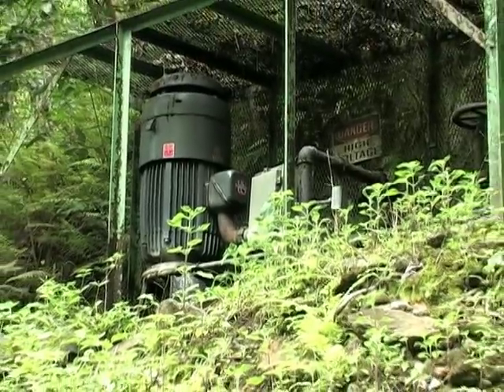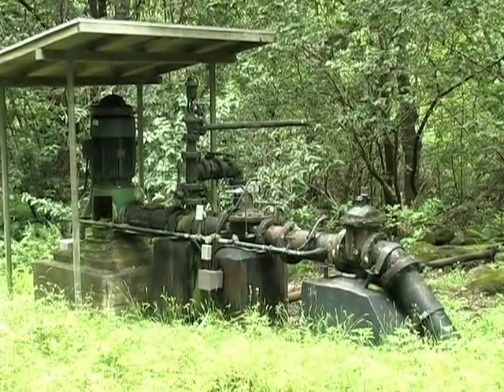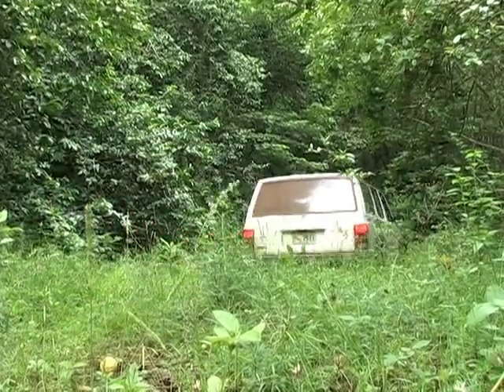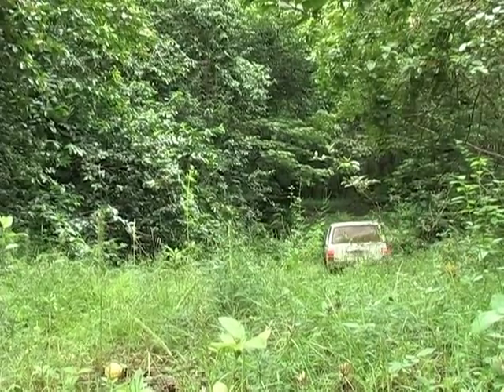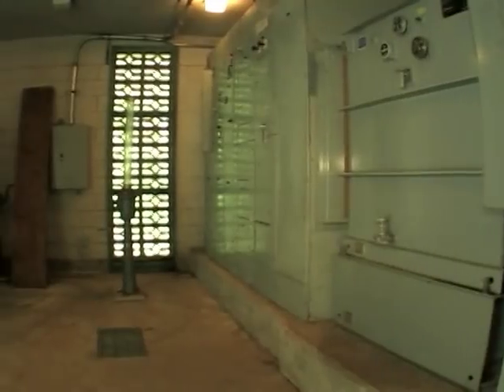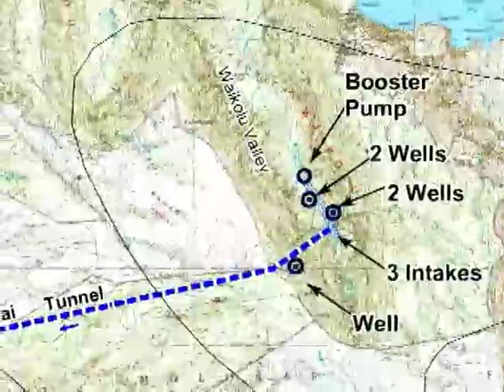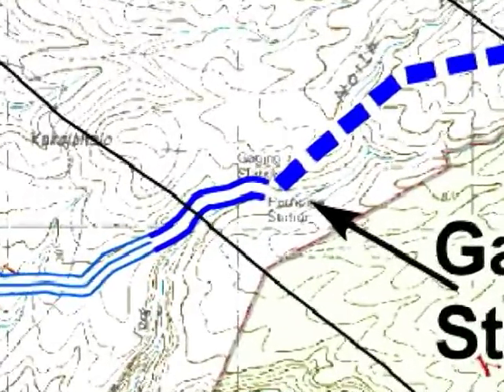Well 23 is at an elevation of 875 feet, Well 5 is at 795 feet, and Well 6 is at 766 feet. Located 260 feet below the east portal of the tunnel is the Lower Diversion Dam. Because of its lower elevation, this diversion requires a pump station to transport water up to the tunnel. The station consists of three pumps that are automatically activated by water level switches.